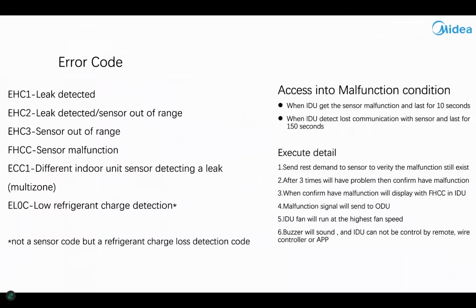So what happens when a leak is detected? I'm going to focus on EHC1 and FHCC, because those are the errors you will probably see out of this A2L. EHC1 is a leak detected. When the indoor unit gets a sensor malfunction that lasts 10 seconds, that's FHCC. With EHC1, it's a 3-strike rule. When the sensor senses a level above 10% of the lower flammability limit, it goes into mitigation.